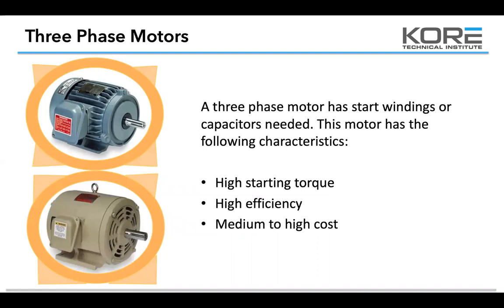The motor has the following characteristics. This should say no start windings or capacitor. So there should be a no in there. Because you're using 3-phase power, you're already getting phase changes through the different windings, because you're dealing with 3-phase power instead of single-phase power. You're not looking for a phase change to happen on the same circuit. You actually have two phase changes happening through the 3 leads there. Make sense? So that's why we don't need capacitors on three-phase motors.